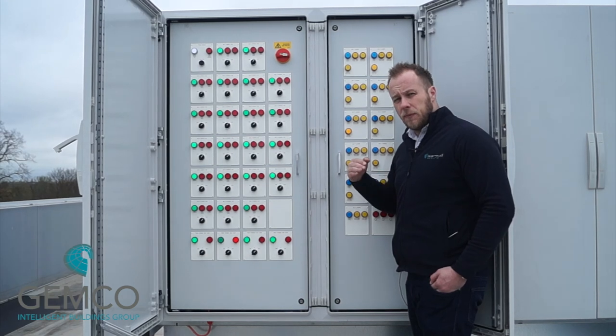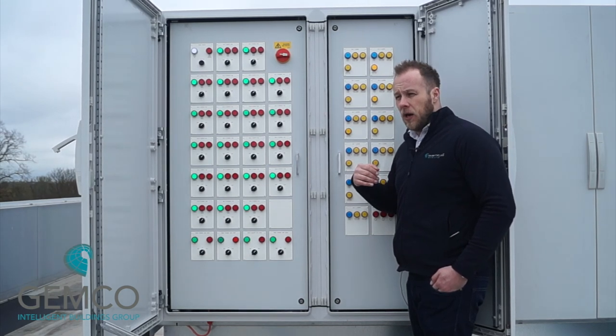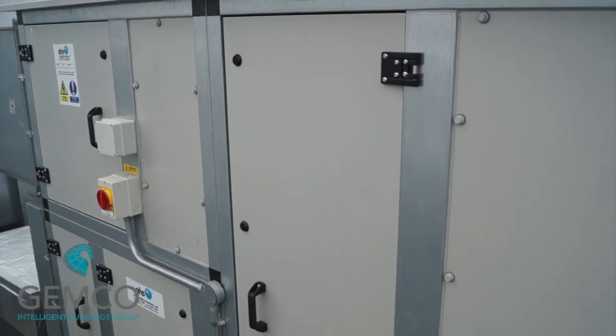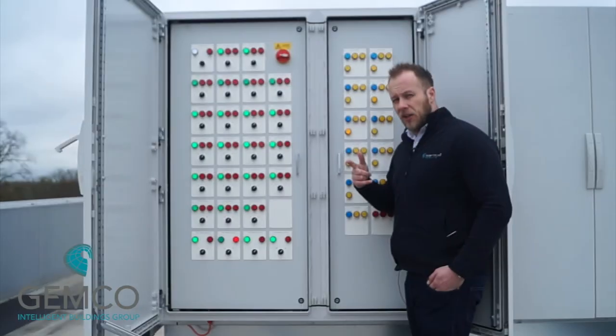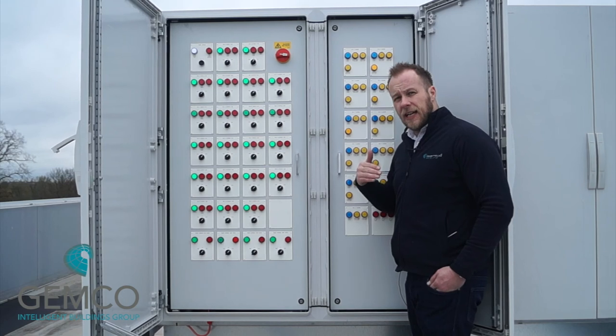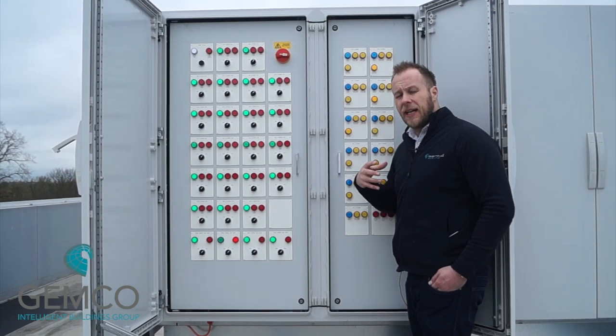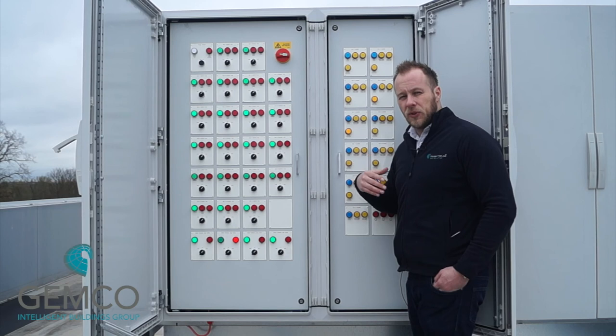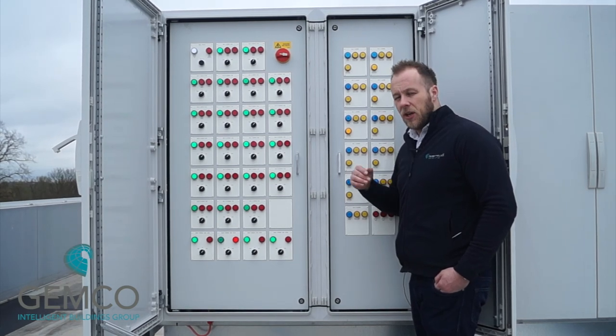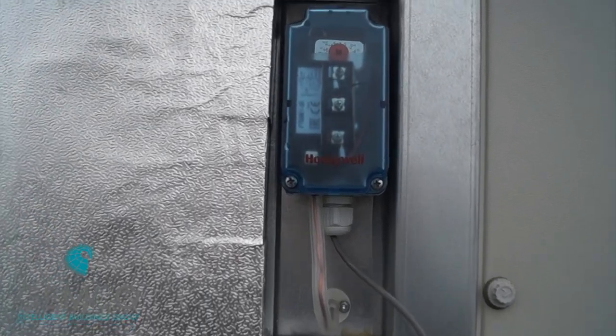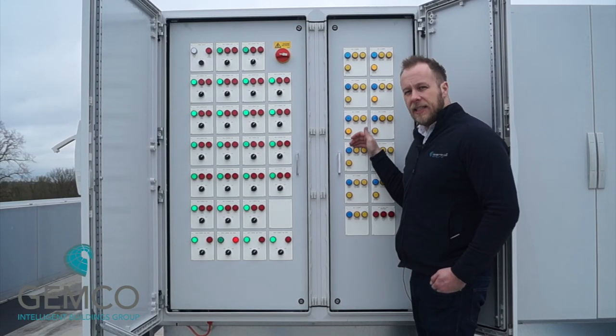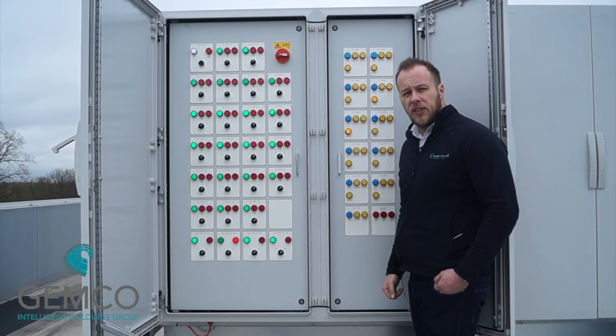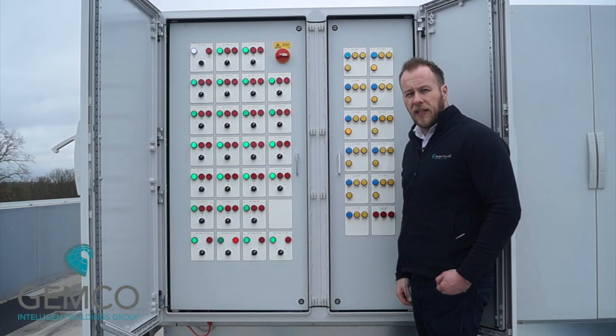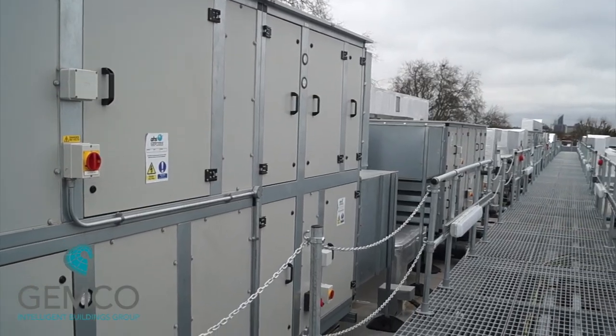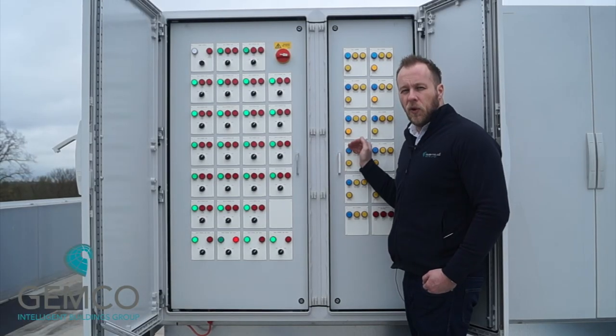The frost stats are all set to 5 degrees. If the temperature goes below 5 degrees, it's saying, well, the thermal wheel must be broken or in fault, the boilers aren't giving me the heat I need, so I better shut down, otherwise I'm going to risk freezing and cracking my coil, and then we'll get all sorts of floods. So if any of these blue lights are lit, that means there's a frost active, and if any of the yellow lights are lit, that means there's a filter dirty. The filters will have to be replaced on a regular basis, and the chances are you'll be replacing them as part of your PPM before these lights come on.